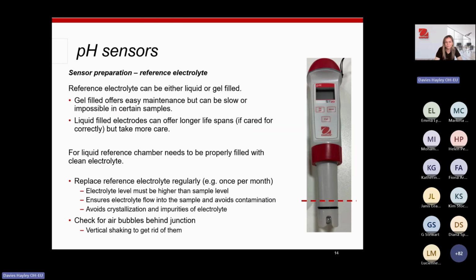Sensor preparation, so the reference electrolyte. I'll scoot over this quite quickly because it may not really relate if we've got a combined electrode that is not refillable with the reference electrolyte. But you can have reference electrolyte that can either be liquid or gel filled. Gel filled ones are easy to maintain, but they can be a bit slow and a little bit impossible in certain tricky samples. But for general aqueous solutions, they should be absolutely fine. And you can get liquid filled electrodes that do offer longer lifespans, only if you care for them correctly, and they do take a bit more looking after.